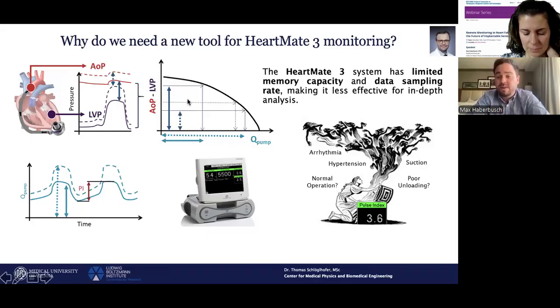And on the left, you can see why this is a problem. The pump's flow depends on the pressure difference between the aorta and the left ventricle, which is AOP minus LVP here. And during each cardiac cycle, this operating point moves up and down along the pump's pressure-flow curve. And the amplitude of this movement determines how pulsatile the flow is, in other words, the pulse index that we just mentioned before.